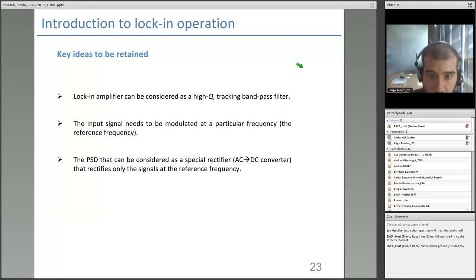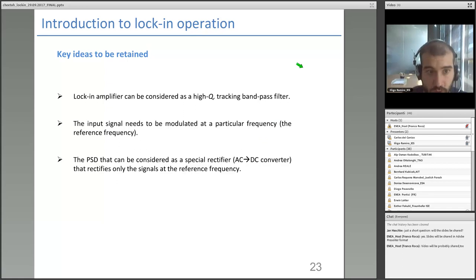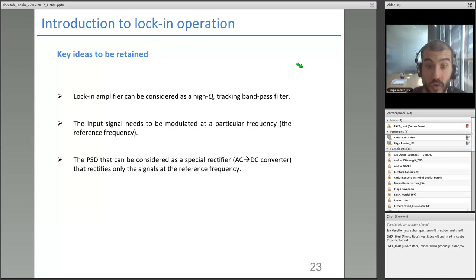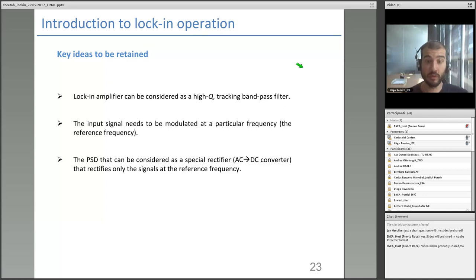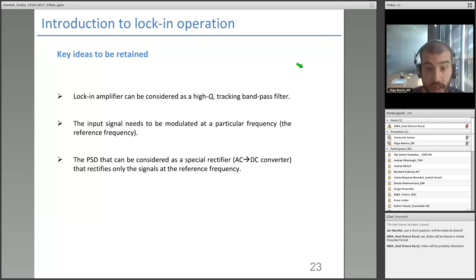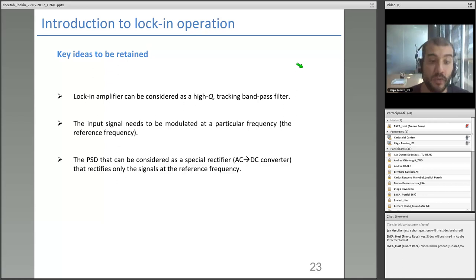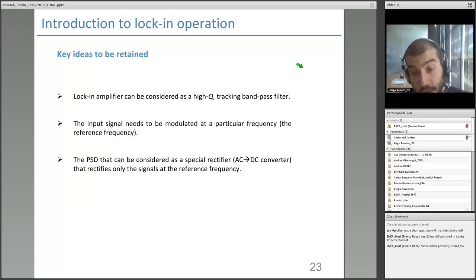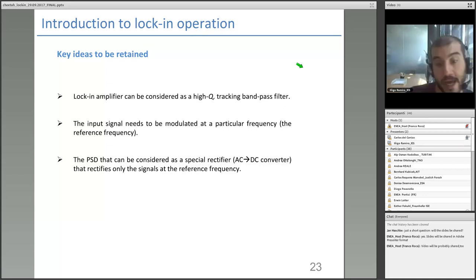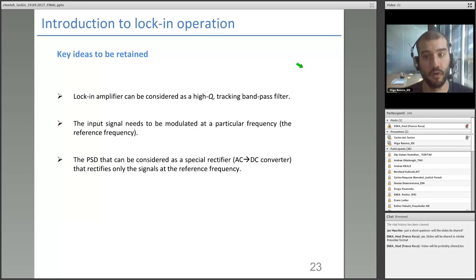To summarize the key ideas of lock-in operation: a lock-in amplifier can be considered as a high-Q tracking bandpass filter. The input signal must be modulated at a particular reference frequency. The PSD can be considered as a special AC-to-DC rectifier that rectifies only signals at the reference frequency, while all other signals exit the PSD as AC and are filtered by the low-pass filter.